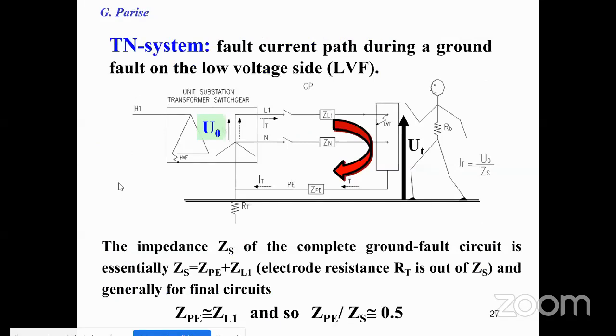In a TN system, when there is a fault on the exposed conductive part, the current does not generally go through the ground electrode, but remains in the system. So the path during a fault consists essentially of the impedance of the transformer, the impedance of the line to the circuit, and the impedance of the PE, the protective conductor.